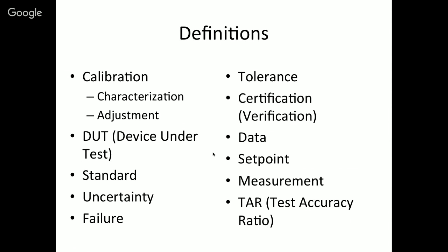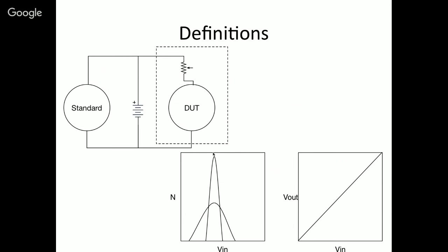A set point, then, is a known point that you're actually going to be measuring. And a measurement itself is an interpretation of a signal that you get from a sensor. Finally, a test accuracy ratio is basically a ratio of uncertainties between the standard and the device under test. And to give you a better idea, so definition-wise, this circuit in our top left corner here has a standard meter and a device under test meter.